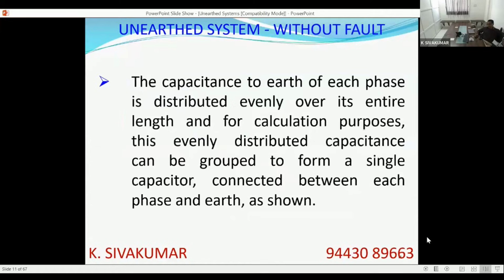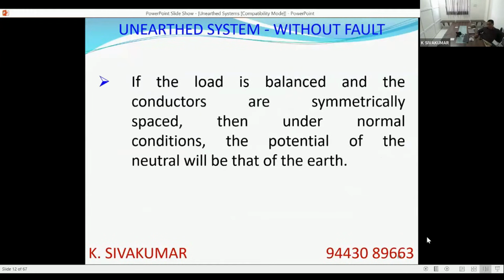The capacitance to earth of each phase is distributed evenly over its entire length, and for calculation purposes, for simplicity, we assume it to be a single bulk capacitor connected between each phase and earth. We assume that the load is balanced and the conductors are symmetrically spaced. So under these conditions, there will not be any residual fluxes, there will not be any residual voltages.